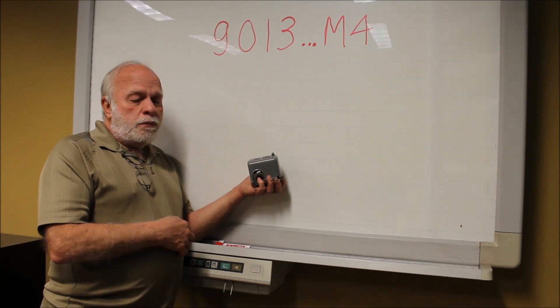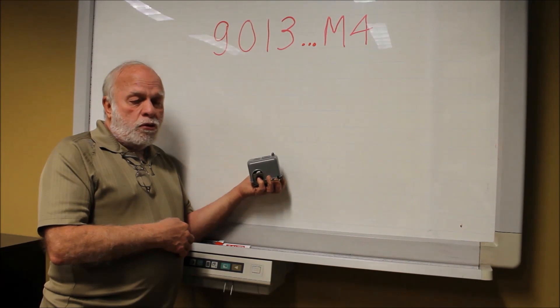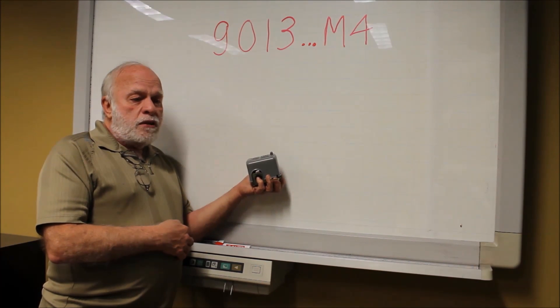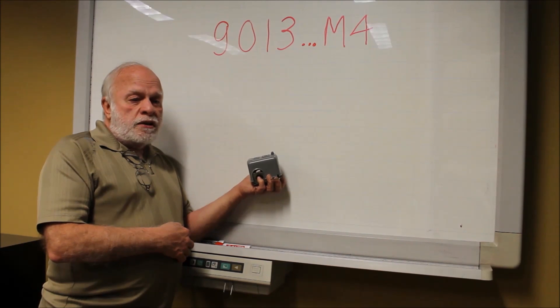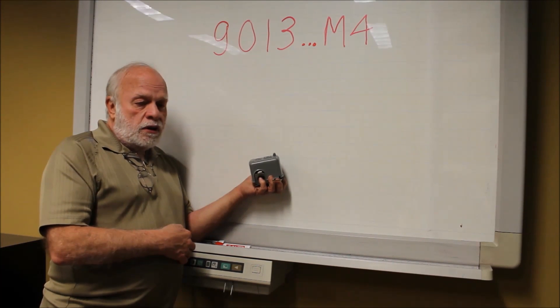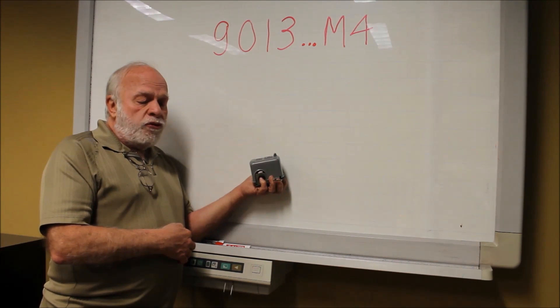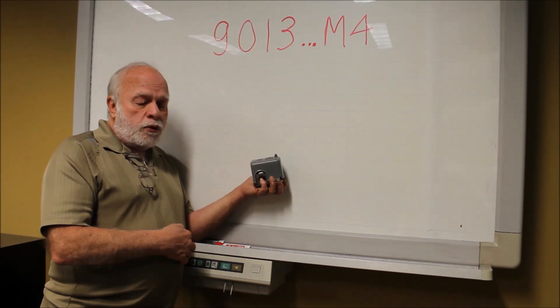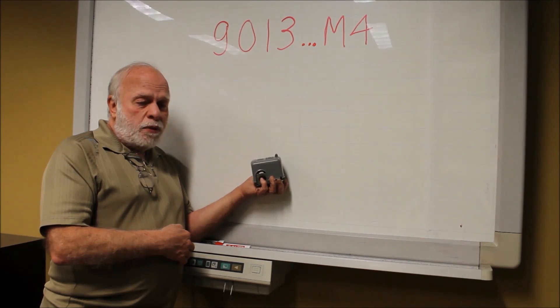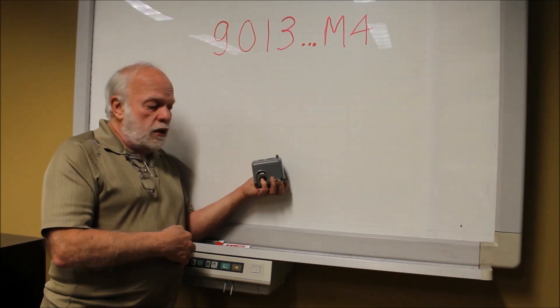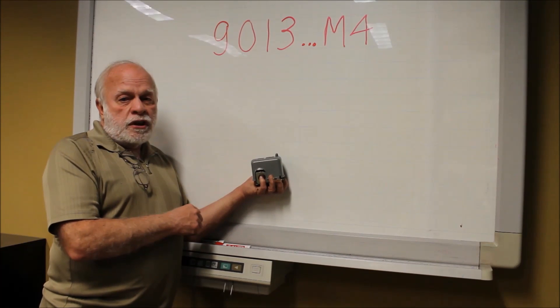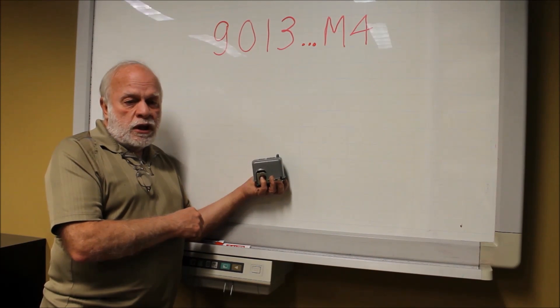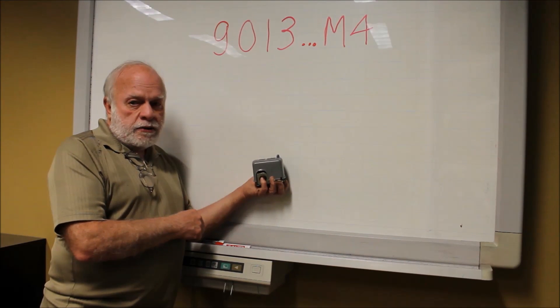The only problem is understanding when the M4 should not be used in some applications. The M4 is designed to cut out when pressure drops 10 pounds below the cut-in. The lever will automatically go to the off position and must be manually reset.